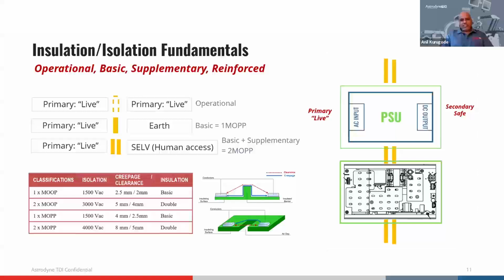What's not stated here, which is where the engineering considerations come in, is what happens when one level of insulation fails and the other one also starts failing, because now it's seeing double the stress. It's like building a column or a rope to hold something - if it fails and the backup also fails, that's not a good design. That's not acceptable for medical systems.